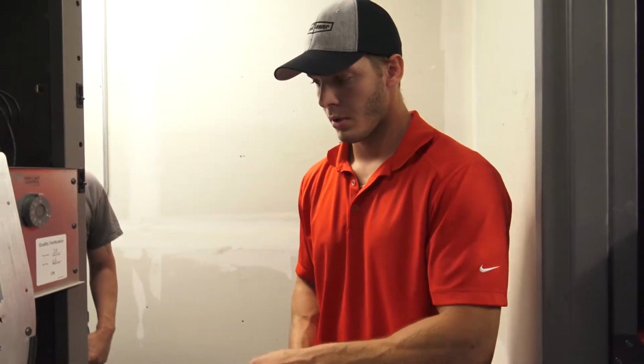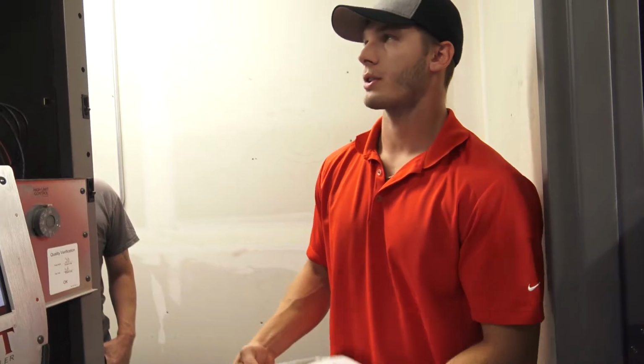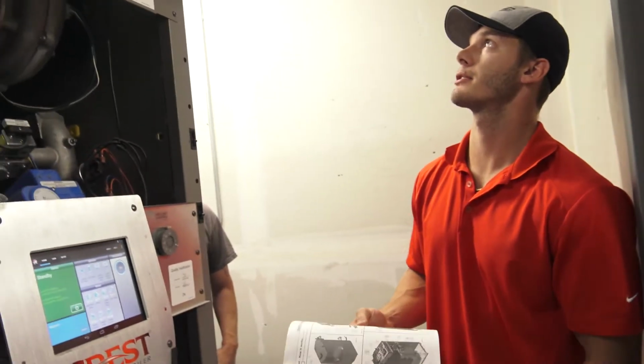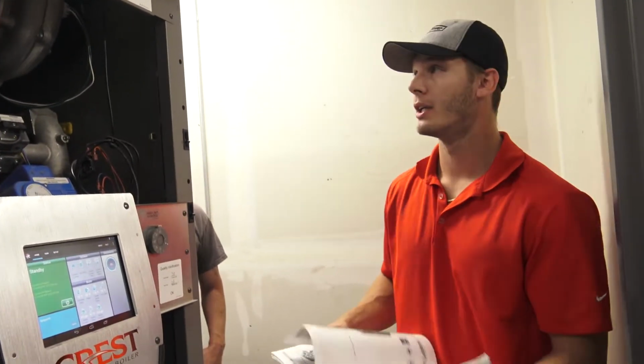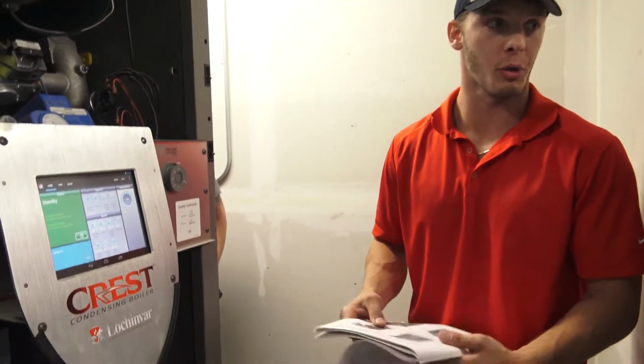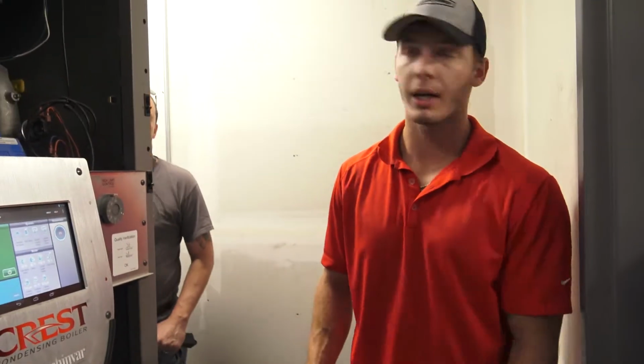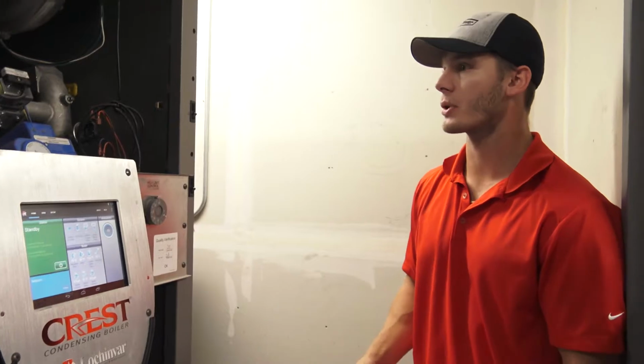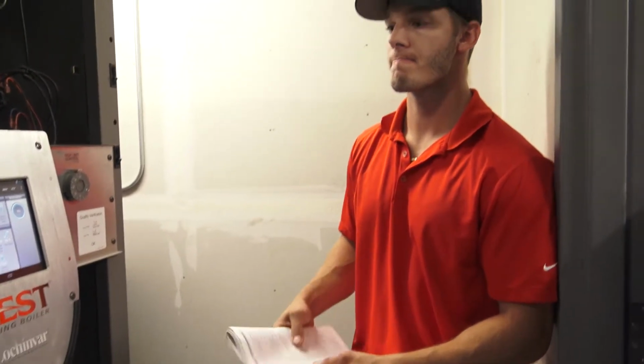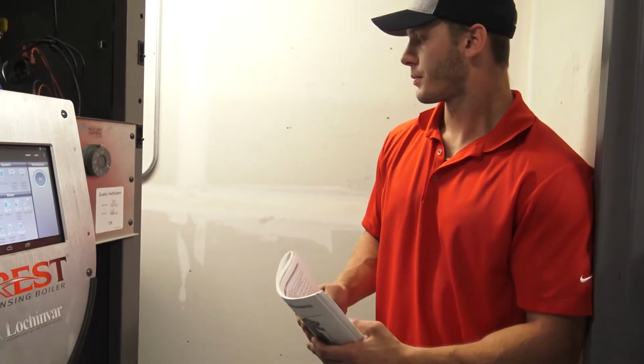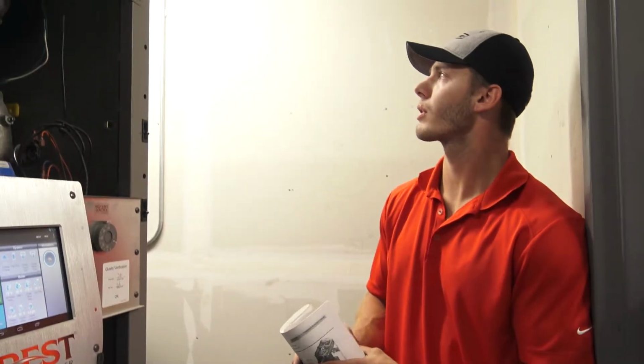The gas piping looks really good. On all boilers, you want to see the regulator at least 10 feet away. This is sized properly.